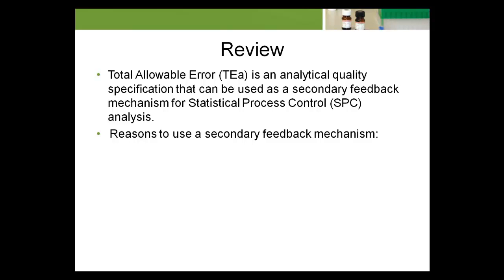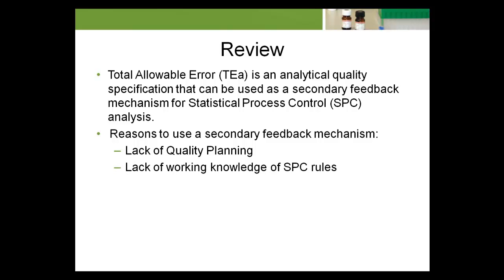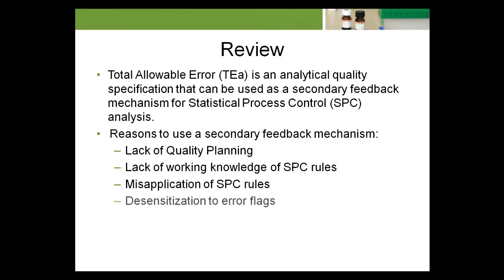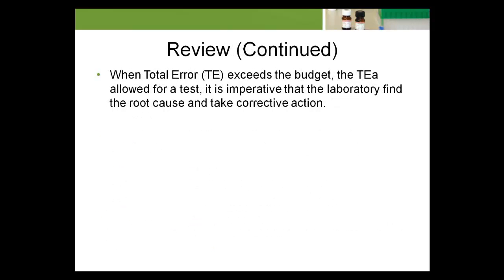Reasons to use a secondary feedback mechanism include: lack of quality planning, lack of working knowledge of SPC rules, misapplication of SPC rules, and desensitization to error flags. TEA is a budget — the overall objective is to limit the entire amount of error, imprecision and bias, to within the allowable budget. When total error exceeds the budget — the TEA allowed for a test — it's imperative that the laboratory find the root cause and take corrective action.